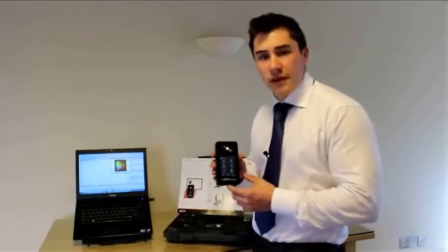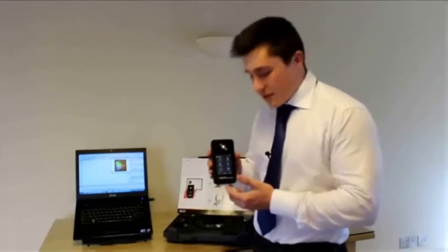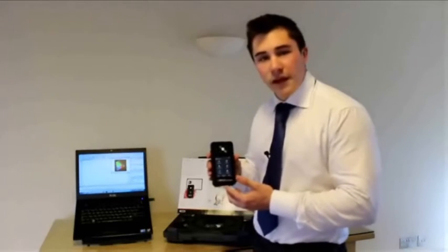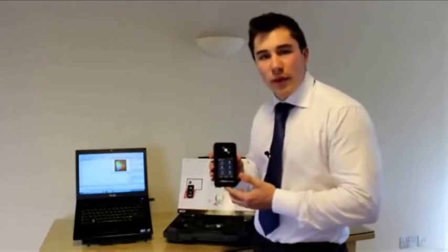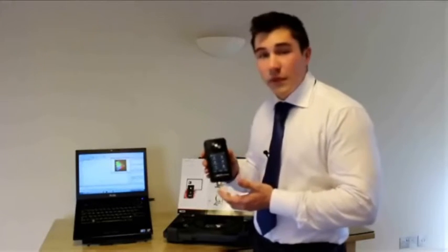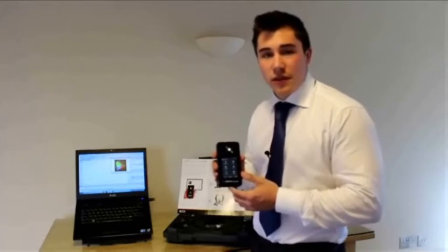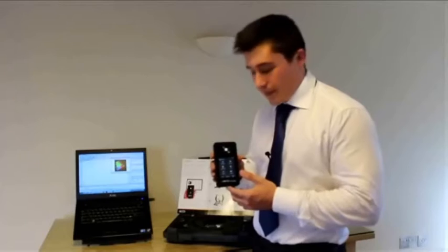The Spectus 1.0 Touch has many unique features, one of which is the temperature compensation mechanism, which is built into the device. This means that the user does not have to wait for the light sensor to warm up before taking a measurement. So measurements can be taken instantaneously as soon as you switch on the device.